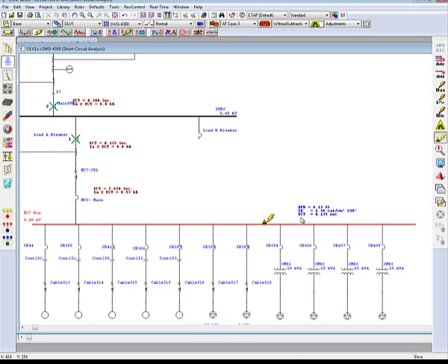And that is reflected with the incident energy and the fault clearing time results shown here on this bus, 0.135 seconds. Now, this current that is passing through the device is approximately 8.5 to 8.8 kA. Let's generate a TCC curve of this portion.